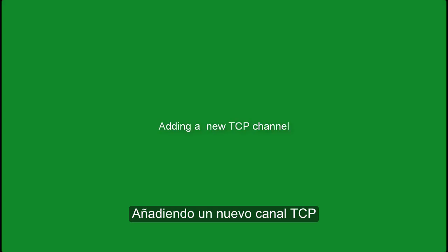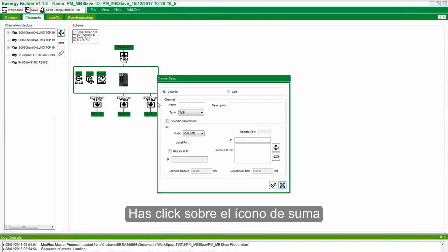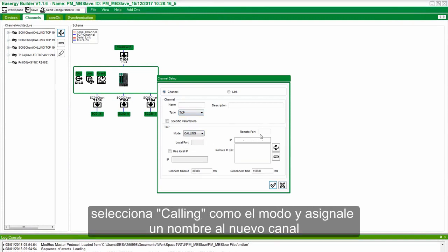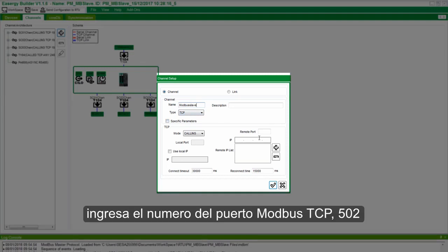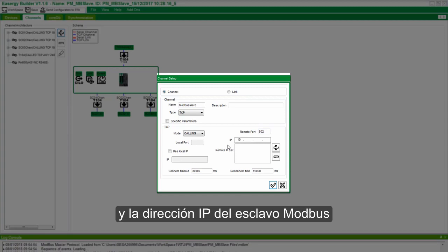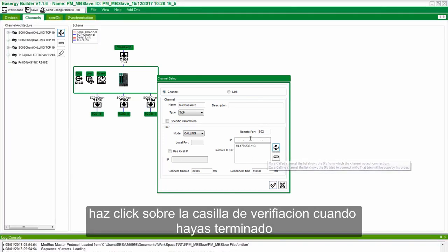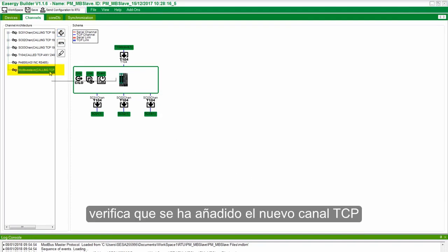Adding a New TCP Channel. Click on the plus sign in the Channels tab. Choose Channel Type as TCP, Mode as Calling, and enter the channel name. Enter the Modbus TCP Port Number as 502 and the IP Address of the Modbus Slave. Click on the checkbox when done and verify the added TCP channel.